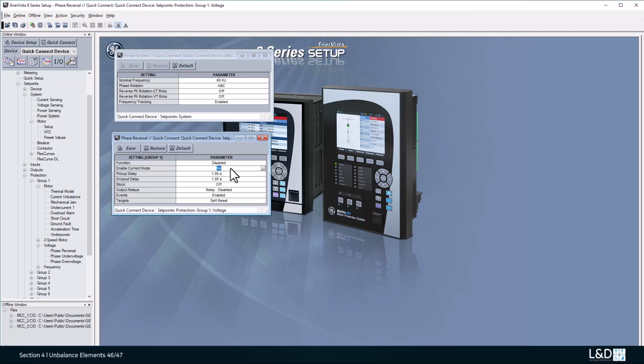With the current mode set to no, the phase reversal detection alarm uses the three-phase voltage only, when the voltages are greater than 50% of the VT. When the setting is set to yes, currents are used to detect phase reversal when the voltages are less than 50% of the VT or the voltages are not available. The current-based method is only activated after the measured currents are above 5% of the motor FLA.